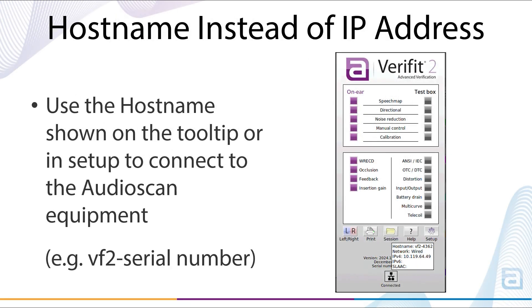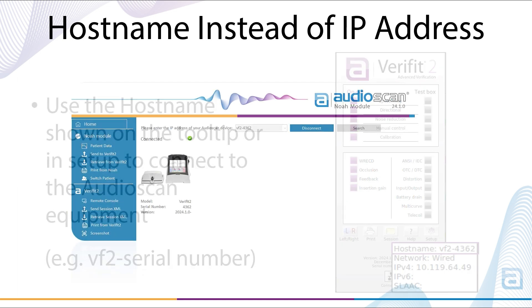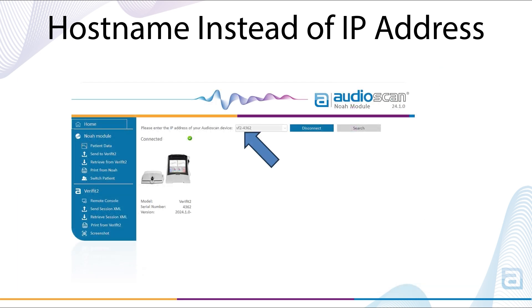Hostname is great to simplify address entry. Using hostname is especially helpful when the IP address changes because the network is not configured to provide a fixed IP address to the Verifit 2 or Axiom. Using hostname will result in a connection even if the IP address changes to another address on the network. This function is also helpful to avoid entering the several characters in an IPv6 address.